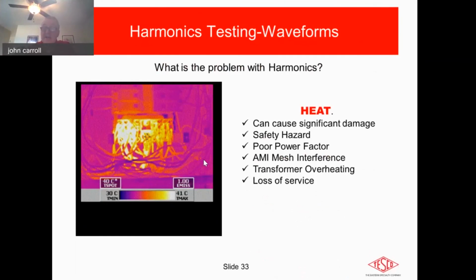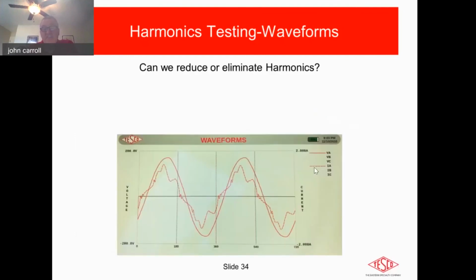In rare cases, it can get excessively heated, and you can get overheating transformers. You can obviously get loss of service, and there's a safety hazard, big one. But one of the issues too is, how does it affect a modern day meter? Well, the AMI mesh itself is a frequency domain mesh. Because this is a frequency domain as well, you can get interference. Not necessarily to prevent the instrument from working, but the meter itself may be interrupted with its mesh, which means it may not be able to report. And then it creates a reporting problem. So having an instrument that at least can give you and identify what you have is really key. And this is a particularly good feature that we put together in this machine.